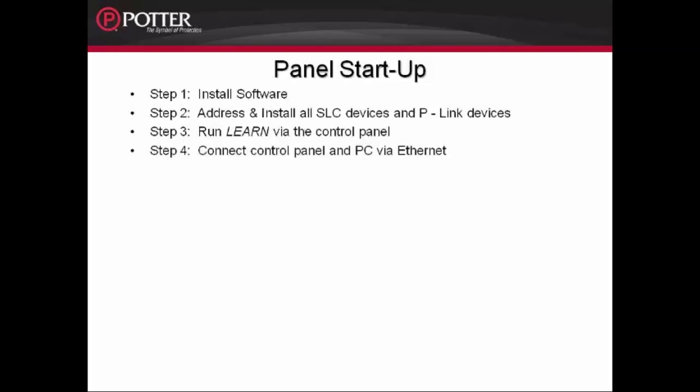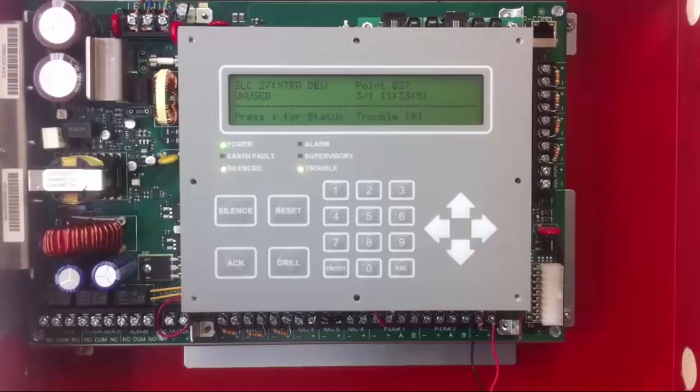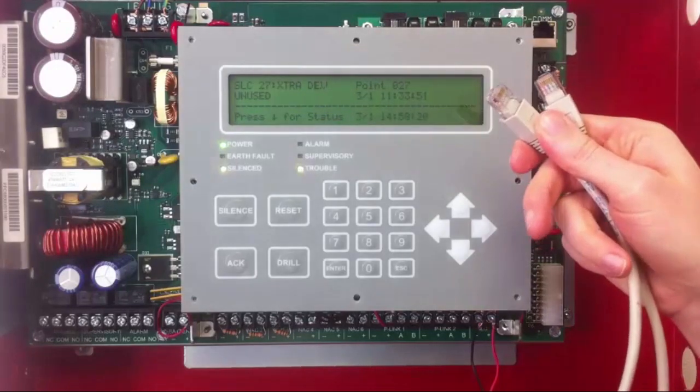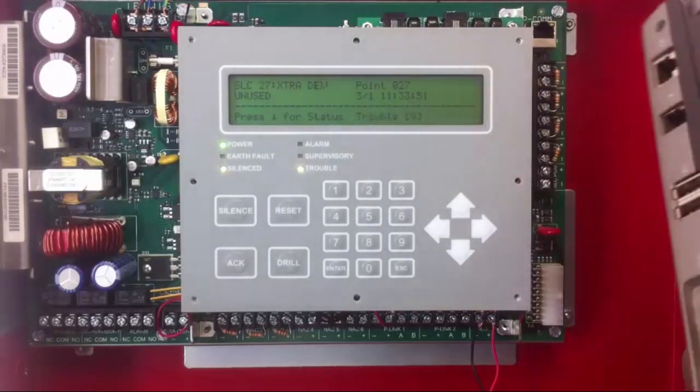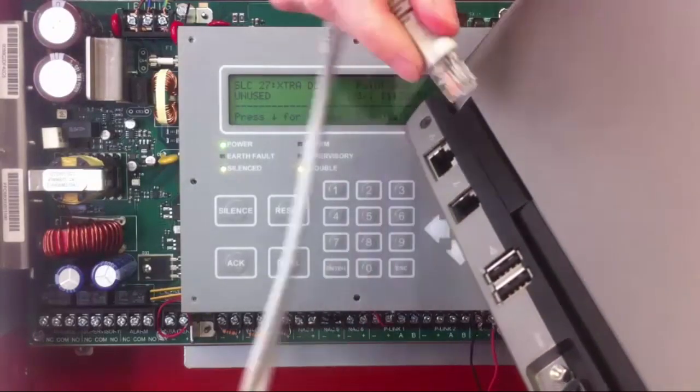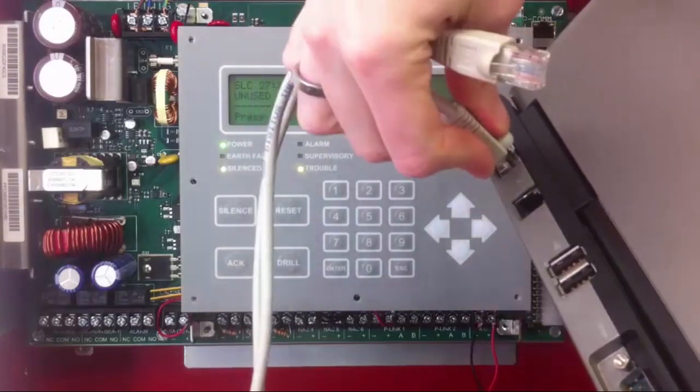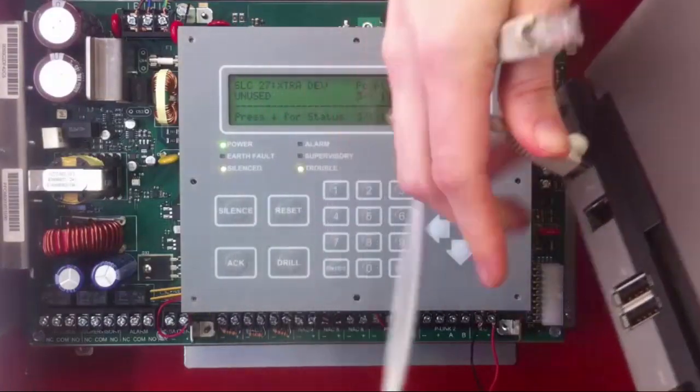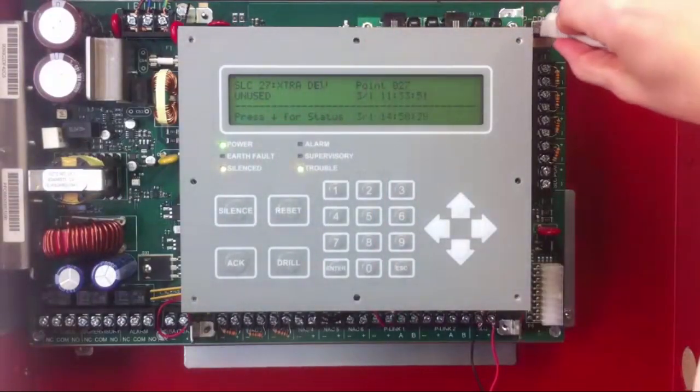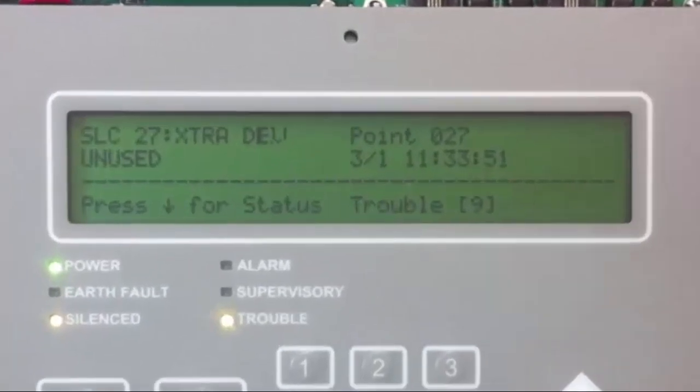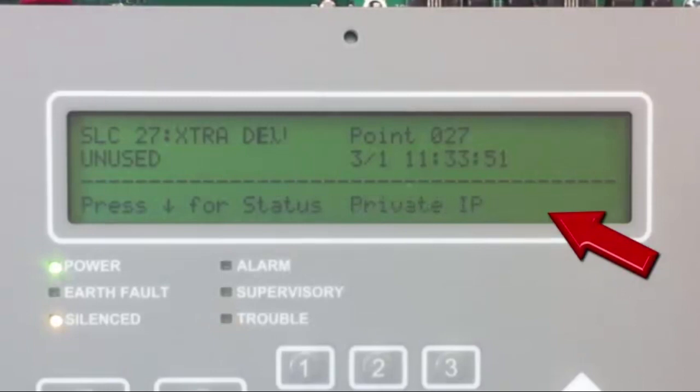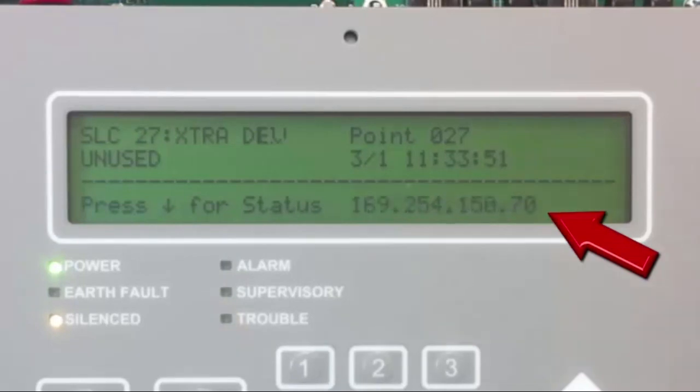After running the Learn function, the next step would be to connect the control panel to your PC with an Ethernet cable. Either a straight through patch cable or a crossover cable will work. When that connection is made, the panel and the computer will work to make a private network. The LCD screen of the Fire Alarm Control Panel will say Obtaining IP, then Private IP, then IP Configured, and it will go between the IP address that it has been assigned and IP configured for about 10 seconds.